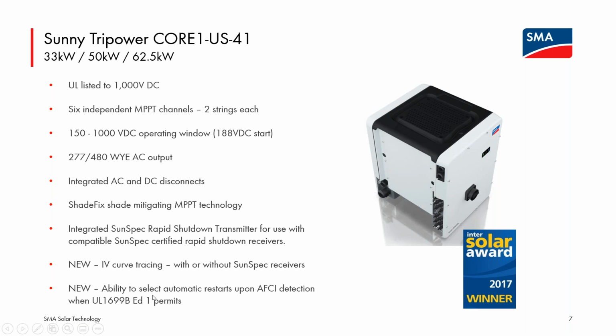And then also there is an update related to AFCI functionality. And again, I will plead a little bit of ignorance on Canadian code on this. What that update on the AFCI functionality allows is you can leave the inverter where if it detects an arc fault, it requires a manual resetting of the inverter to go back into service. But the new firmware also allows an option where you can allow the inverter, if the arc that it detects is under a certain incident energy and is extinguished within a certain time frame, it will allow the inverter to automatically restart. So I don't know if that is per se allowed by code in Canada, but that is a feature now that the firmware unlocks in these units, and I'll talk about it in a little bit of detail so that you understand how it operates and if it is of use to you, how to turn it on.